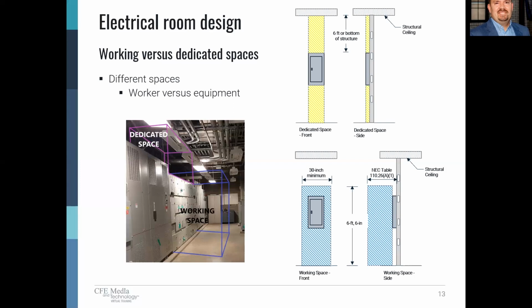equipment. While not specifically required in code, one of the things that we do as a best practice in our specifications on a project, we often will require the contractor to physically mark out the working clearances on the floor with either tape or painted lines. And this provides a visual reminder to the occupants of the space that the space is specifically used for access for the equipment and is not to be used for things like storage, etc. Dedicated space, on the other hand, is really about accommodating the equipment and allowing for conduit entry and exit from the equipment, and also for perhaps bus duct or cable tray. Brian is going to talk about dedicated space in greater detail in the later slides.